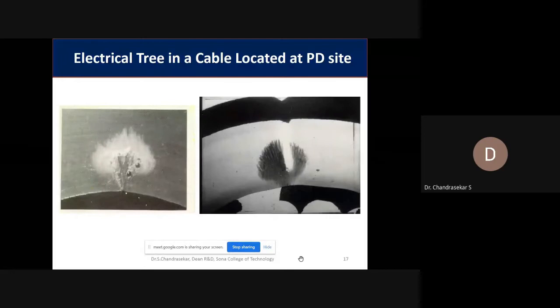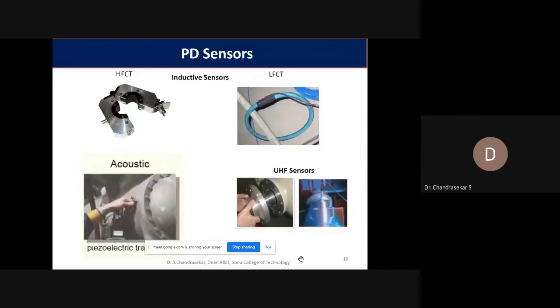Similarly, this is a partial discharge occurring inside the cable. You can see in the picture, in the cable insulation, the arcing slowly developed, and it is now growing and moving towards the ground electrode. You can see it is forming like a tree, so it is called an electrical tree in a cable. It is mainly due to partial discharge activities in the cable. While manufacturing, if some void or cavity is formed inside the insulation, it will slowly lead to partial discharges, and finally one day that particular portion of the cable will burst or a short circuit will happen. So these are all the major problems in cables and transformers.